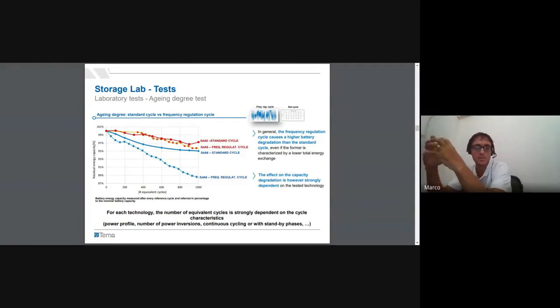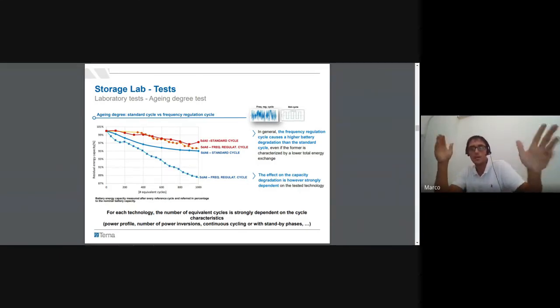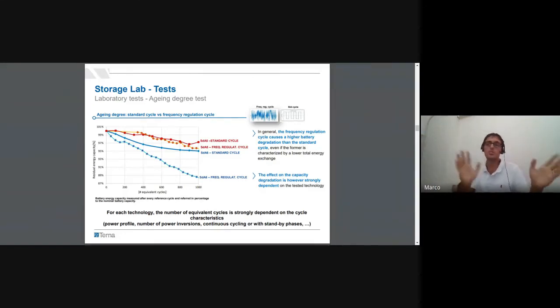We tested this technology with two different cycles: the first is a standard cycle, full charge and full discharge continuously; the other is a frequency regulation cycle. You can see that this technology ages differently depending on whether it's a standard cycle or a frequency regulation cycle - it has very high aging if there's a lot of switching between charge and discharge. Technology number 5, the red line, doesn't show different aging depending on purpose - the aging seems the same whether used for frequency regulation or a standard cycle.